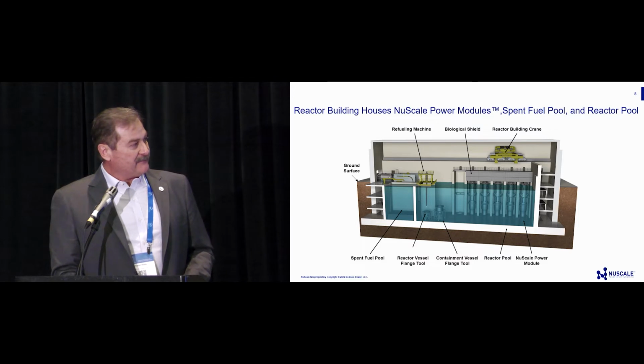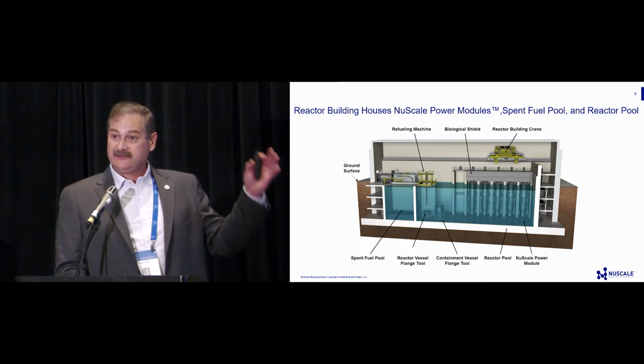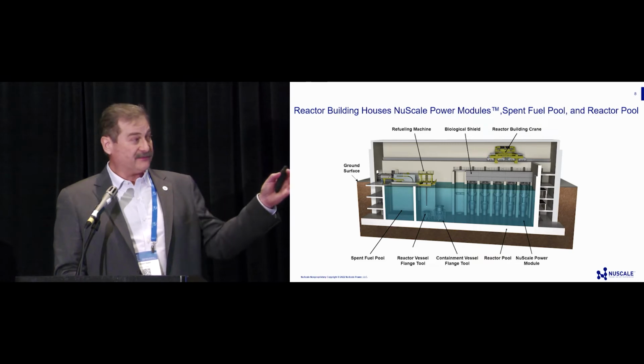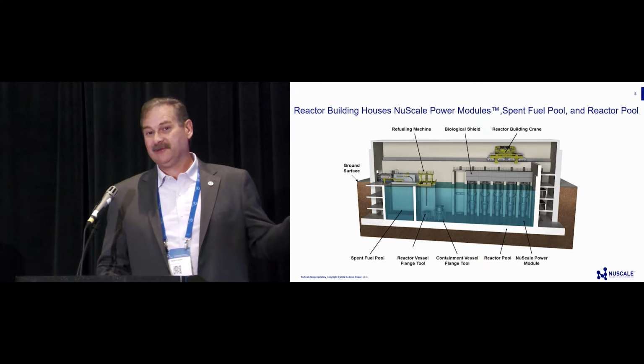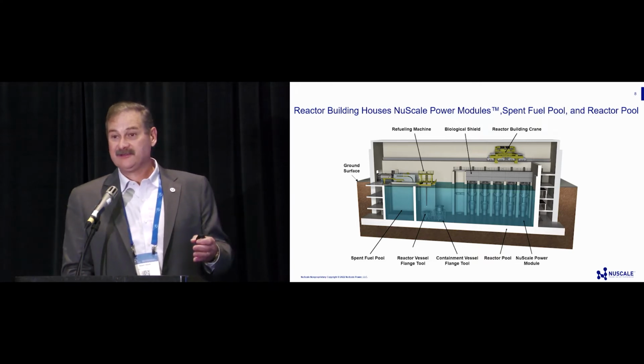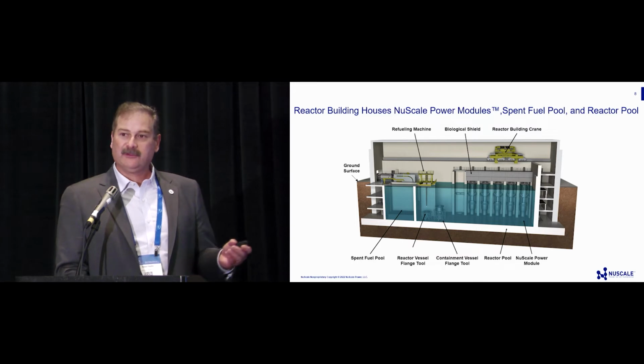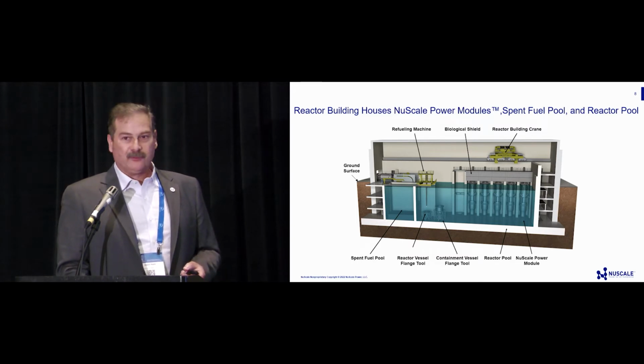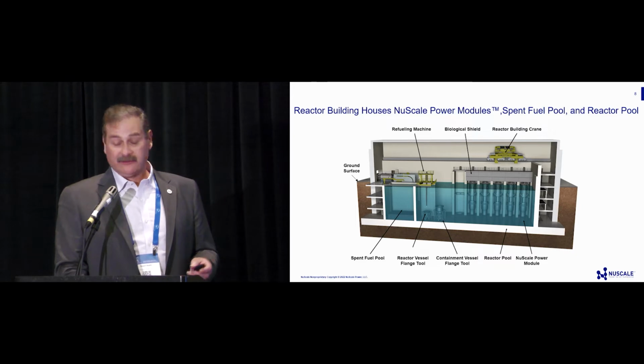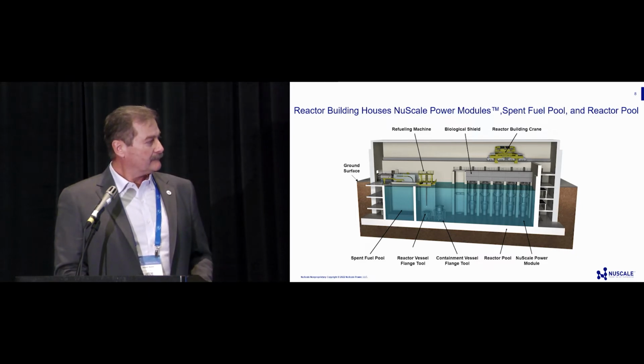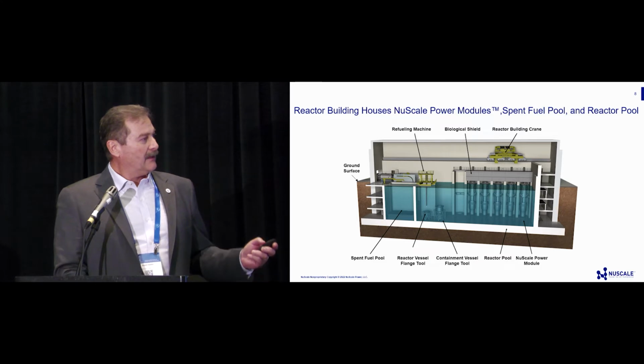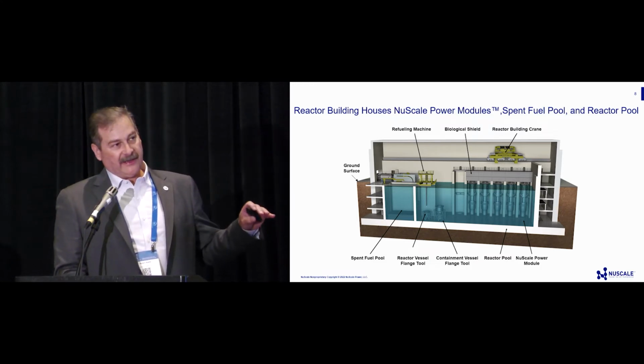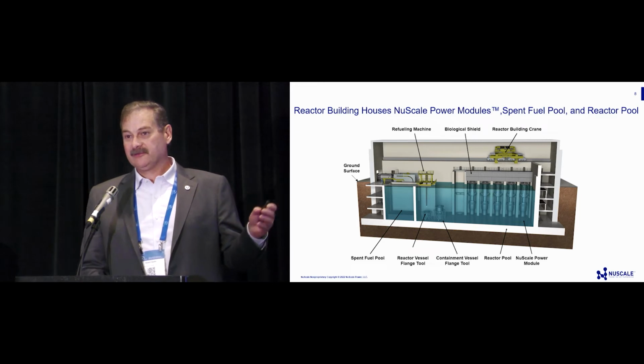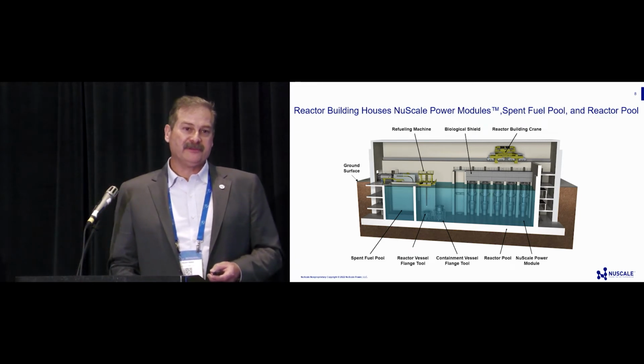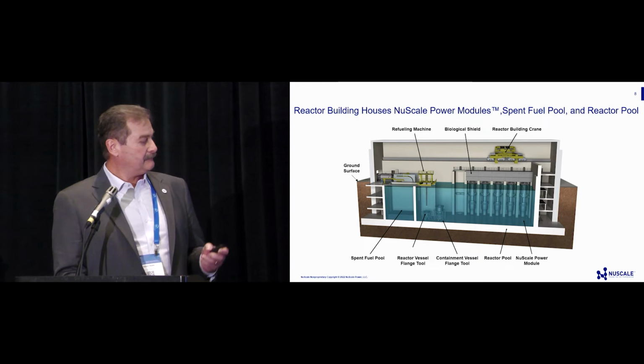As another side view, this would be a 12 unit plant, so just a cutaway view. Our 6 module plant looks identical to that. They call it the ultimate heat sink. The water that sits in the reactor pool is about half the size for a 6 unit plant as it would be for a 12 unit plant. 12 unit plant's, I think it's roughly 12, 13 million gallons of water in that pool. You can see the reactor building is all below grade. It's an aircraft resistant enclosure, so it's both seismically secure and protected from above.